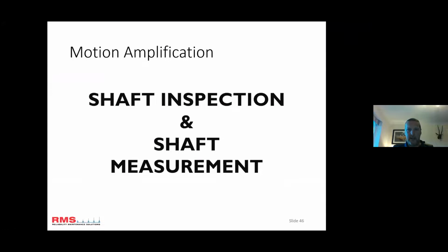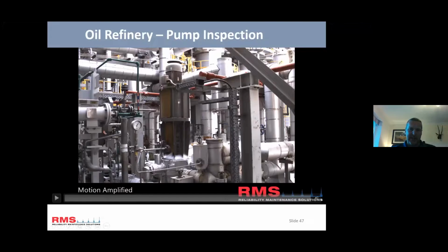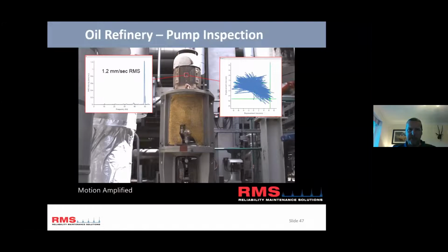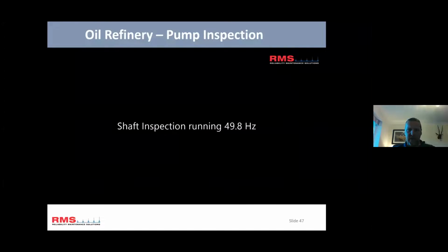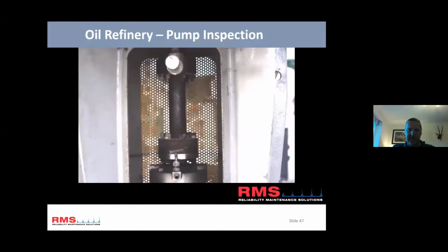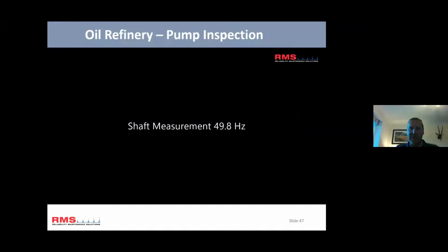Another tool we can use the camera for is a bit like a strobe, really. This is on an oil refinery. We've just done some standard motion amplification there. It wasn't particularly bad on the pump itself, but there was a lot of shaft movement on this shaft, not good. So that's running there, and we've frozen the image so we can use the technology just like a strobe to visually see.